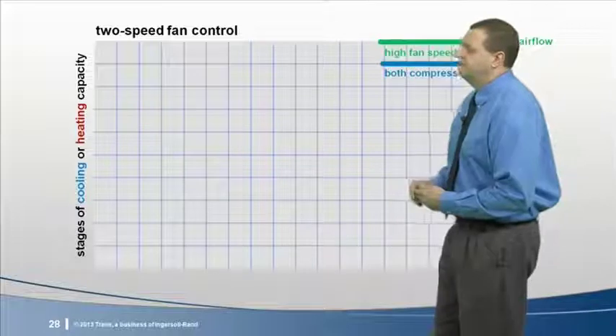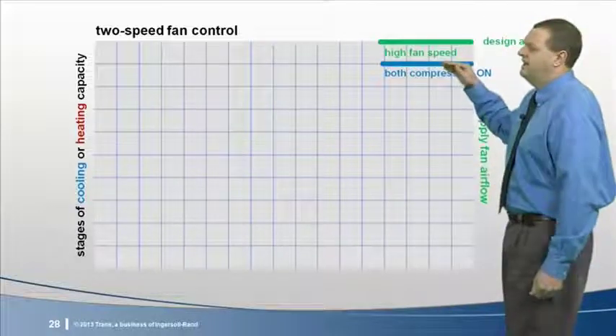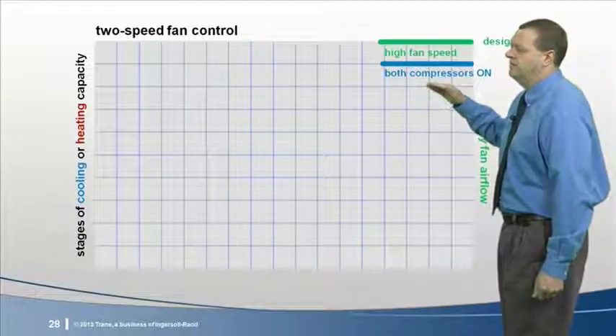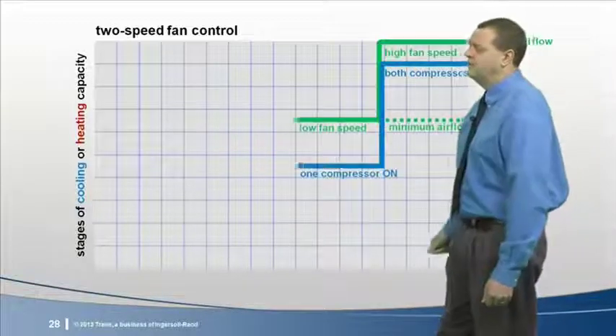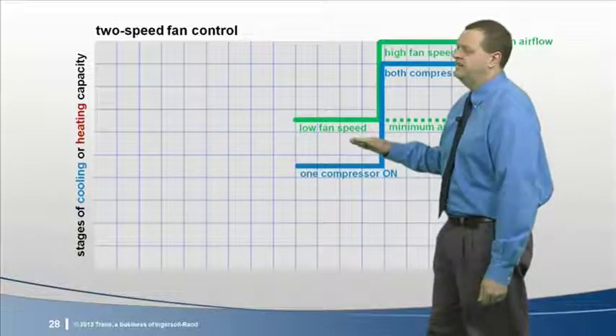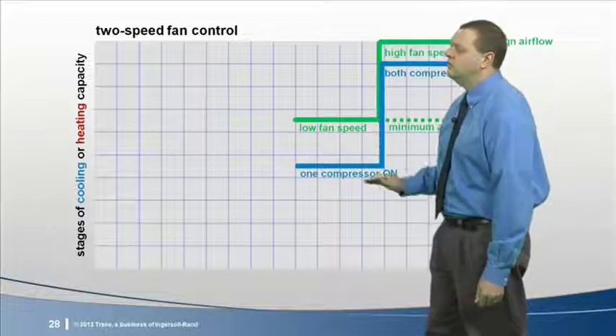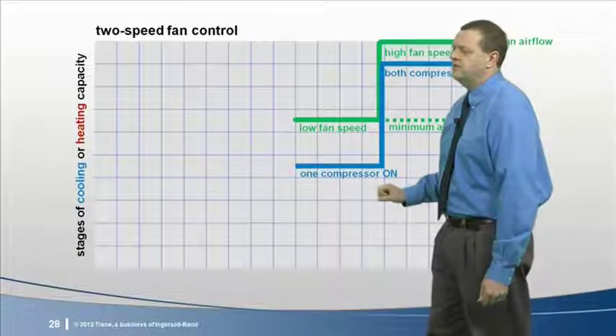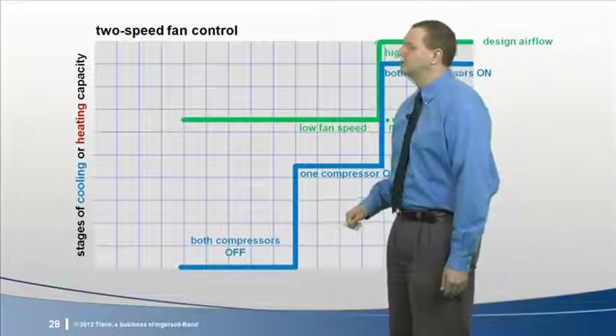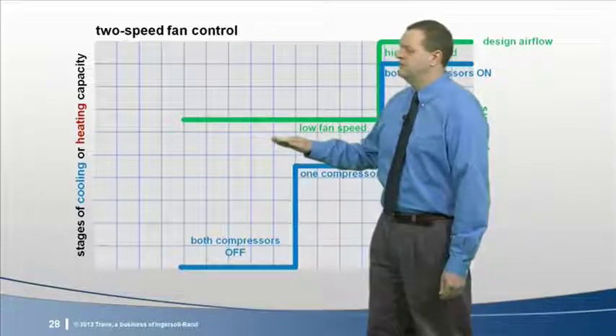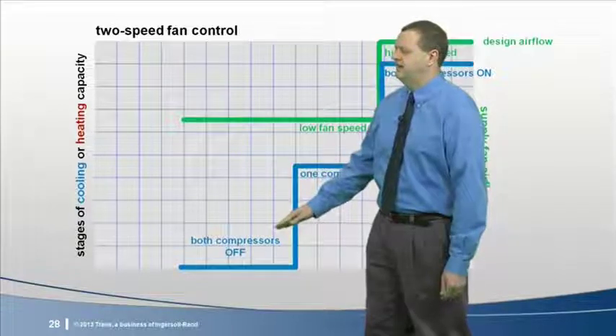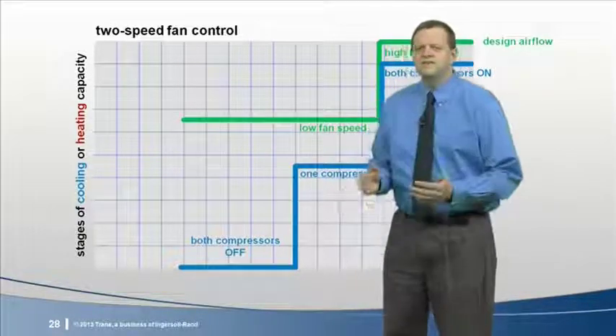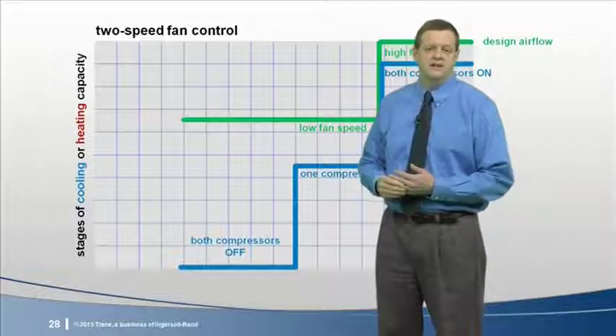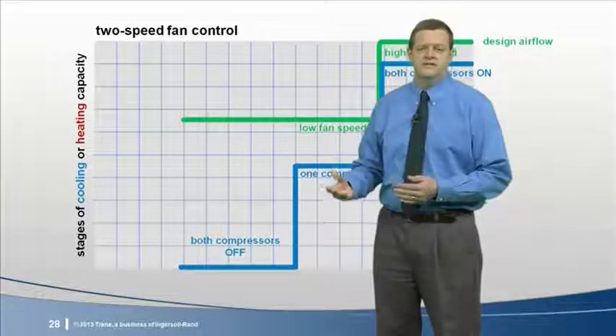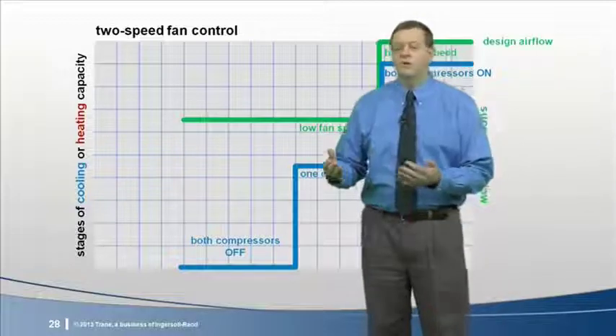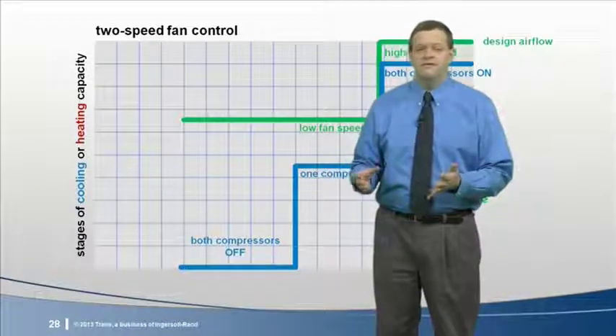When the thermostat calls for both stages of cooling, the supply fan operates at high speed with both compressors on. When only one stage of cooling is needed, the fan turns down to low speed with only one compressor operating. Then when the thermostat calls for no cooling, the fan continues to operate at this low speed, but both compressors are shut off. So basically, fan speed follows the compressors as they're turned on and off. If both compressors are on, the fan's at high speed. If only one compressor is on, or if they're both off, it's at low speed.